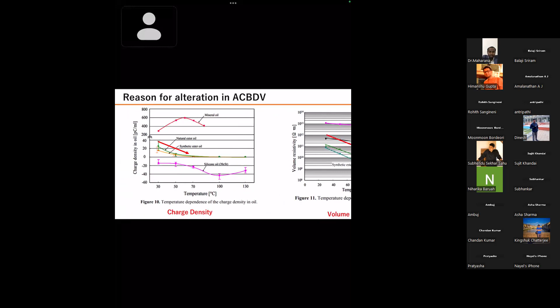So in this first graph, the charge density of the oil, in both cases, in our cases, is decreasing. Density of the charges decreases with temperature. That means the charges are not getting accumulated with each other. That is the first reason we have cited. And volume resistivity is another significant possible physics behind the decrement of dielectric strength at high temperature. So volume resistivity is the resistance to the leakage current through the body of the insulating material.